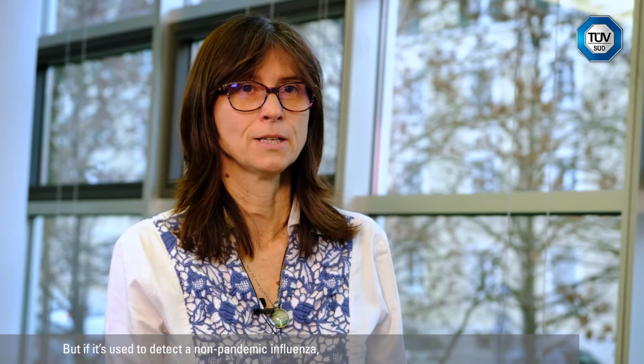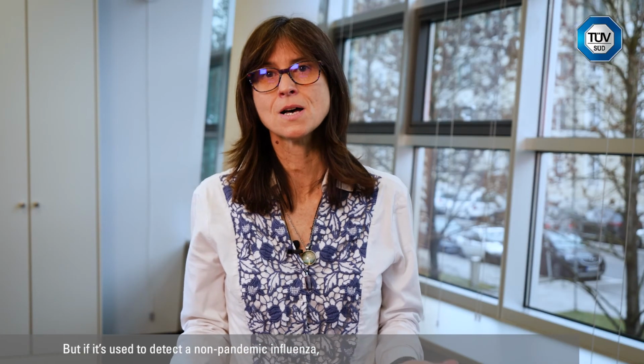Another interesting example is the case of influenza. If the device is intended to be used to detect the presence of highly virulent pandemic influenza, it will be class D, according to Rule 1. But if it's used to detect a non-pandemic influenza, then the device would be class B, according to Rule 6.